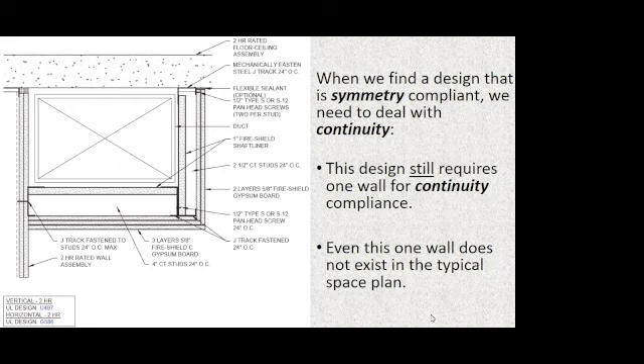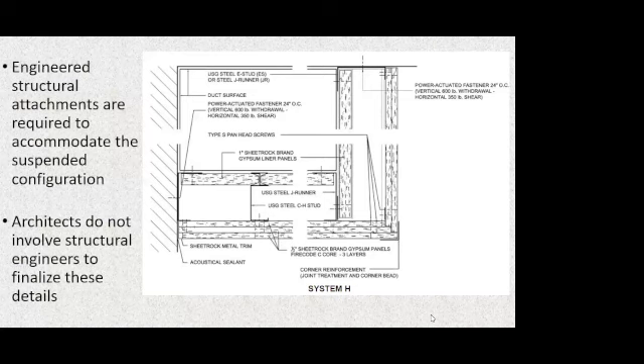That's where we are. I've been on my mission now with this fire rated duct industry to fix what I think is one of the most broken industries in fire protection. And I'm at this place where half the people that I educate tell me they're not going to do it until someone makes them. So for example, the architects who see this design and I tell them, the fine print down here says you must have a structural engineer design the anchoring system, because the wall design that has been scavenged by the Gypsum Association for this design says that. And it says that because the typical wall only has anchors designed for pinning to keep the wall from tipping over during the fire. They're not bearing a load. They're not bearing even half a load.